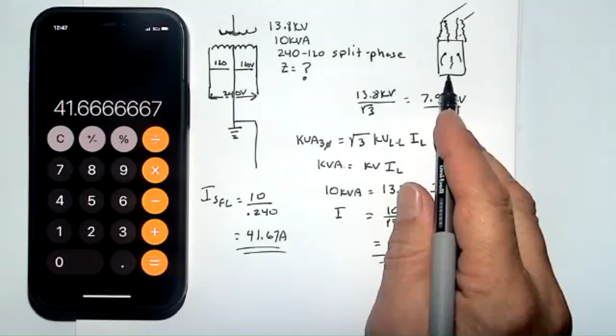But the utilities will actually push these transformers up even more, and they'll let you draw maybe almost 2 times the normal kVA because they'll just let them blow off the poles. But the reality is you're never going to approach the 200 amp panel that's in your house. So why do we put 200 amp services in? Well, we don't know. If they have a 10 kVA transformer, they may upgrade that to a 25 kVA transformer or maybe 50 kVA. So we don't know. The capacity of the service coming into your house is what really dictates your breaker, and not necessarily the full load amps in this case.